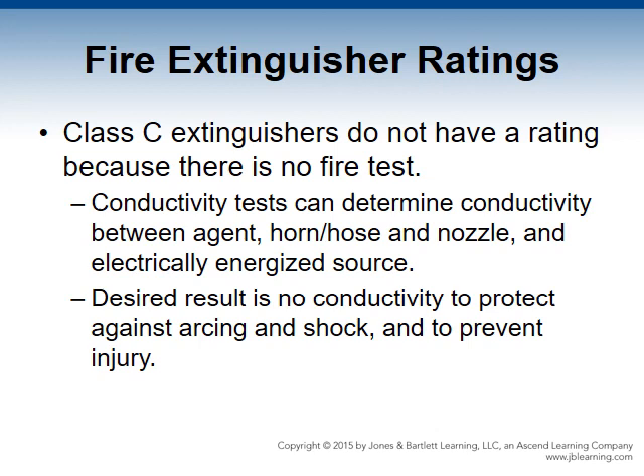Class C extinguishers do not have a rating because there is no fire test for Class C agents. There is a test to see if there is conductivity between the agent and the horn, hose, and nozzle, and an energized source. The agent is discharged onto an electrically charged plate placed 10 inches away from the extinguisher nozzle. The desired result is that the agent and equipment are non-conductive, so there is no risk of arcing, shocking, or injury to the operator.